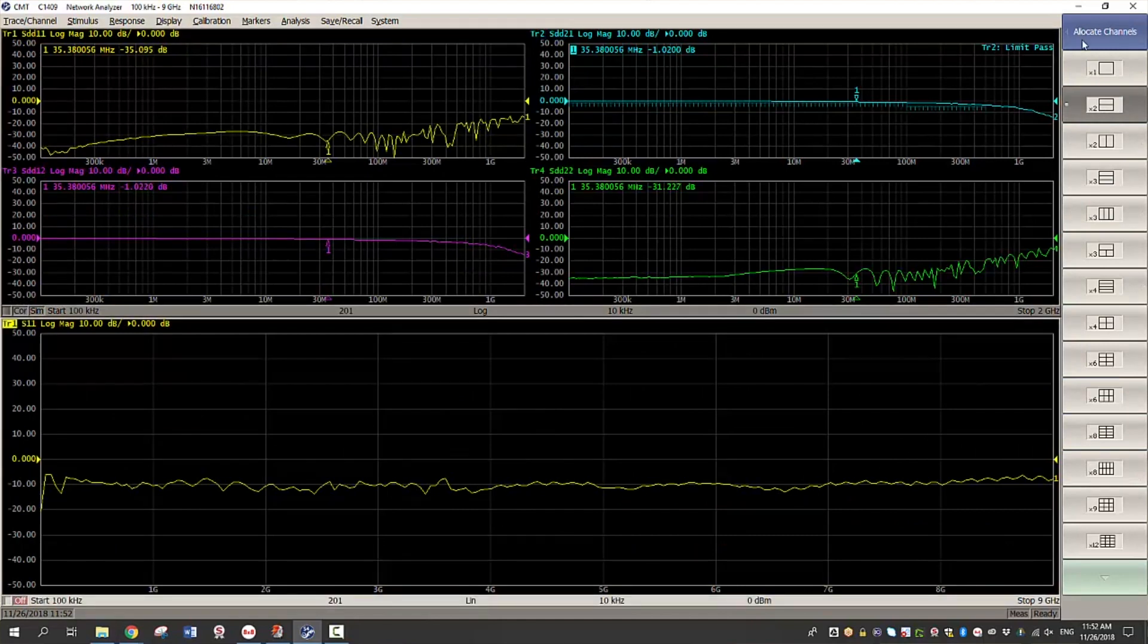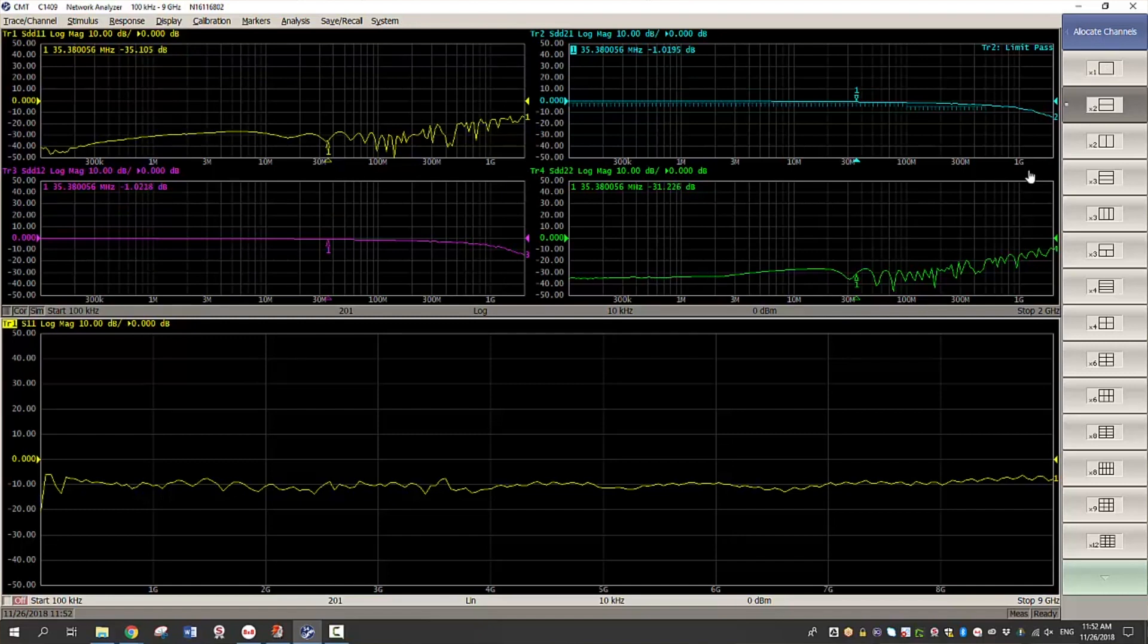Now since we are adding a second channel we have to repeat calibration, de-embedding and balance measurements again.